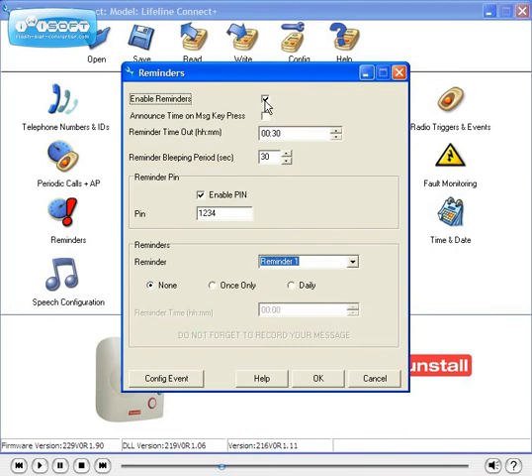The reminder timeout function determines the length of time the Connect Plus unit will wait before raising an alarm call when a message is not acknowledged.